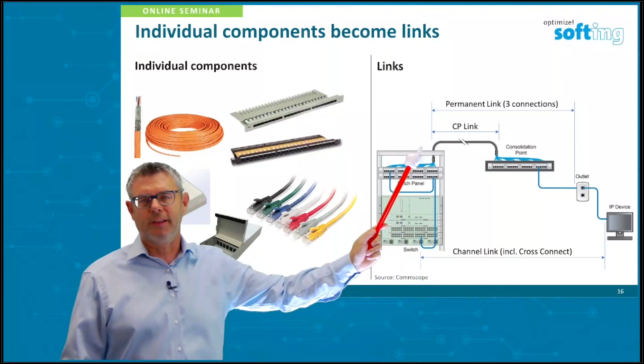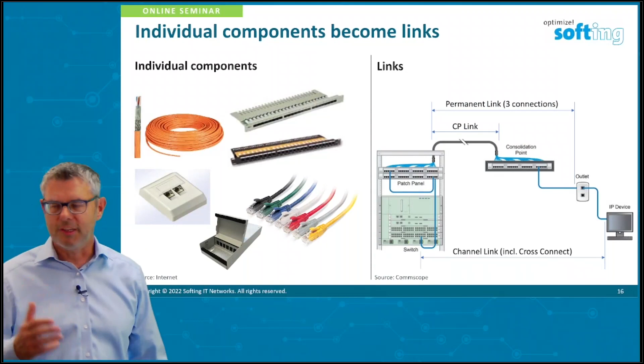This is the permanent link. If you add the patch cords needed to connect to the switch on one side and the PC on the other, it's called the channel link. The channel link is the complete transmission line, but you only measure the channel link in case of trouble or fault with an existing link - it's not the type of measurement used for acceptance testing. Let's stop here; more details and a closer look at the different link models next week in the advanced training course.